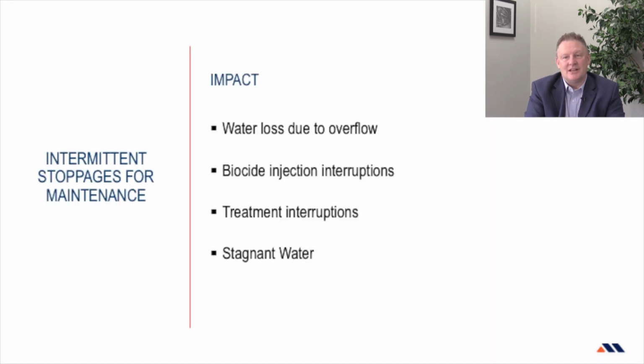As previously mentioned, some stoppages are not always seasonal, as some occur for maintenance. Even if the stoppage is planned, water quality and system protection can be impacted. For example, some systems have significant water losses as the system is designed for overflow. This creates a water quality imbalance during startup that can affect corrosion protection as well as biocide injection.